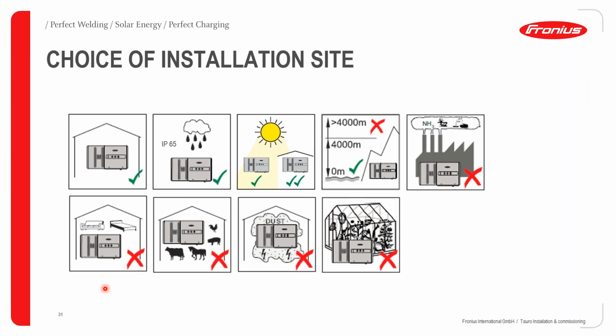Again, don't install a Tauro in a bedroom, but I don't think this would even be happening, due to it being a commercial inverter. Don't install it in a barnyard where maybe there's animals that could chew on the cables. Don't install it in a highly static environment, because as you know, ESD is very bad for power electronics, and our Tauro is not immune from that. And please don't install a Tauro in a greenhouse, because the ambient temperatures could easily rise above 50 degrees Celsius.